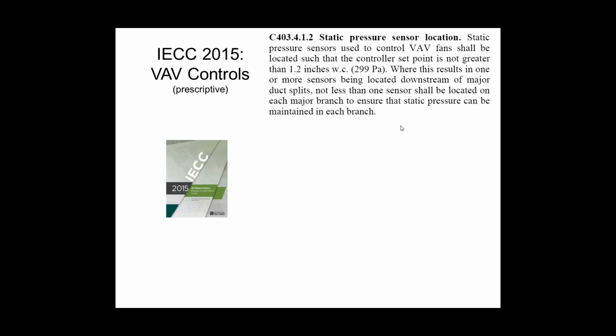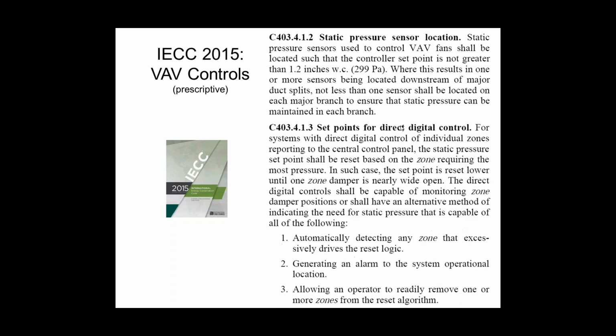The two-thirds rule is now gone. You probably have to locate it further down, and you may have to have multiple sensors on multiple branches to get this accomplished. If you have DDC controls on your VAV system, and let's face it, almost everybody has DDC controls on their VAV system, hardly anybody uses pneumatics other than some old hospitals. But as soon as you put DDC controls in, there's lots more code things that kick in. They don't make you do it on pneumatics because pneumatics is completely inflexible and obviously not possible to do most of these things realistically.